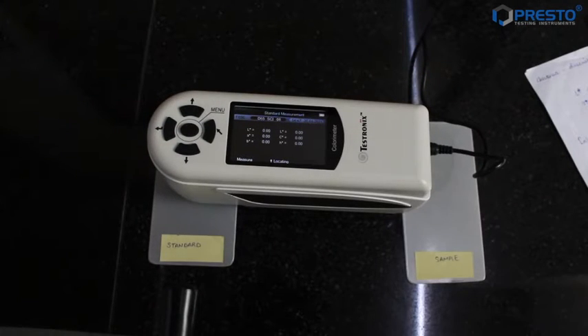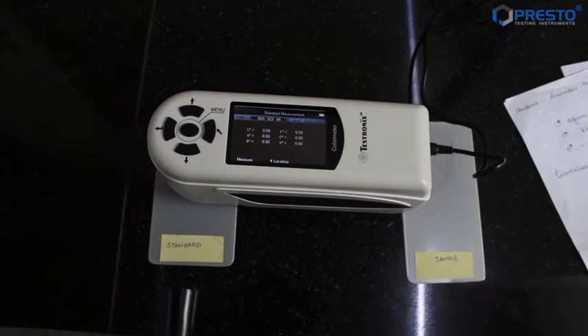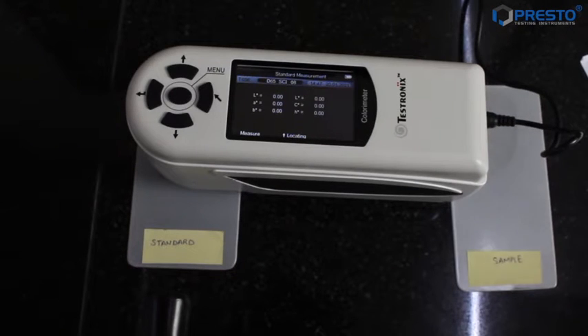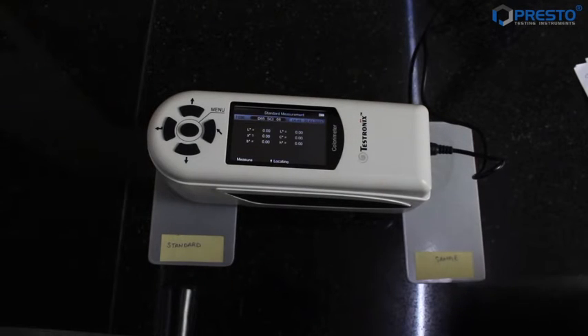LABCH values of the standard color, where L defines lightness or darkness value. Plus L means the sample is lighter, negative L means the sample is darker. A defines red-green value. A positive value of A indicates the sample is redder and a negative value of A indicates the sample is greener. B defines yellow-blue value. A plus value of B indicates that the sample is yellower and a negative value of B indicates the sample is bluer. So for capturing readings, press the testing key.